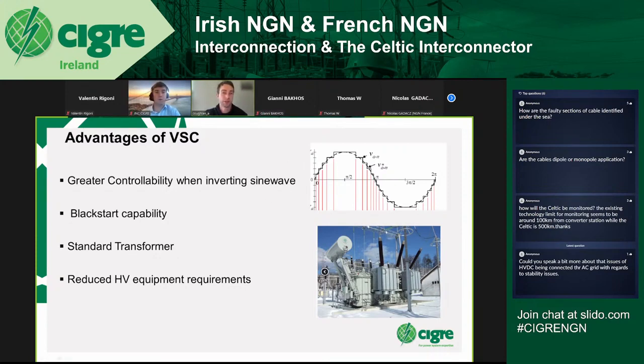Second point: LCCs need this waveform to work, but VSCs don't - they can be triggered at any point along the waveform, or even if there is no waveform, meaning they have black start capability. We heard it mentioned earlier that EWIC has black start capability, so if the Irish network lost all voltage or lost power, all we would have to do is start a diesel generator in EWIC, start up the house load, start up the cooling for the converter station, and then as long as France has power, we can use that to start our network.